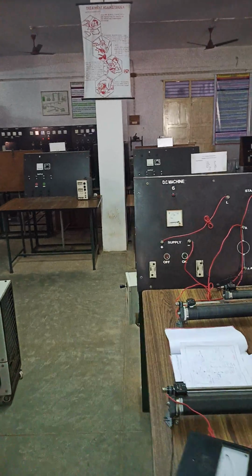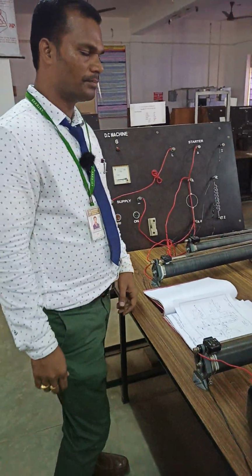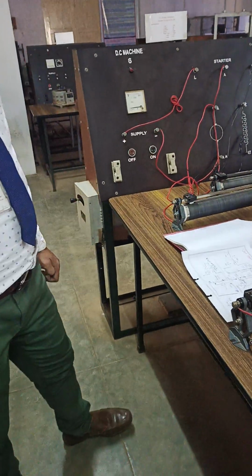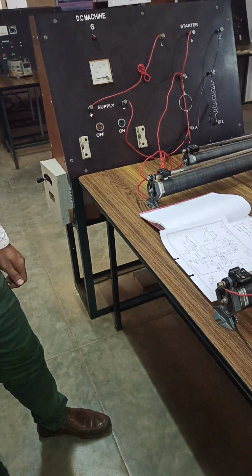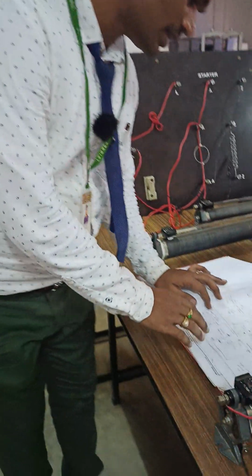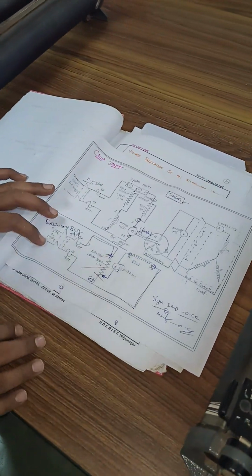Now we are going to find out the voltage regulation of an alternator using the ZPF method, the zero power factor method, and we are going to determine the ZPF characteristics of an alternator, and we are going to find out the regulation by the Potier method. Let's try to see the circuit diagram. So already it is explained in the MMF method also.